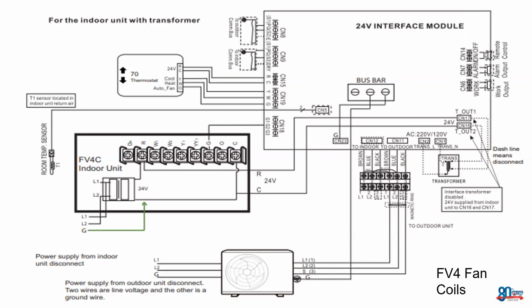Okay, and the last thing that we need to focus on is there is a supplied sensor that comes with this kit on CN5. You'll see this little T1 sensor on here. You need to make sure that you take this T1 sensor and the extension kit that comes with it. I believe it's up to 10 to 15 foot on there, so that we can relocate this return air sensor into the return air boot on the actual furnace or the air handler itself. Make sure we can read return air temperature. If you don't relocate this temperature sensor in there, the system's not going to be able to read an accurate return air, and of course, we're not going to be able to control room temperature for what the customer wants.